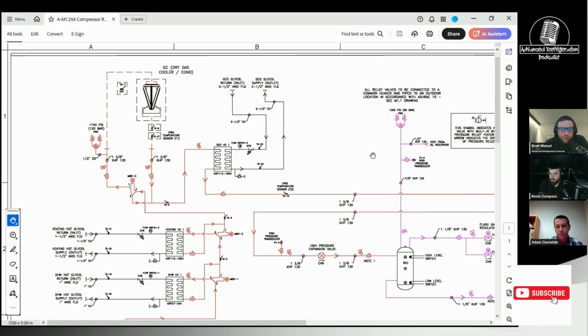When you guys design that, Adam, are you doing reverse flow, like through the suction out through a bypass line, or are you doing like Corno does, where they have the oversized valve and shove it directly through the liquid line back out the suction? We don't do that. Typically, we divert and then come back down a discrete header. Okay. Or go back up to the inlet of the gas cooler to get recondensed? It dumps into the receiver.